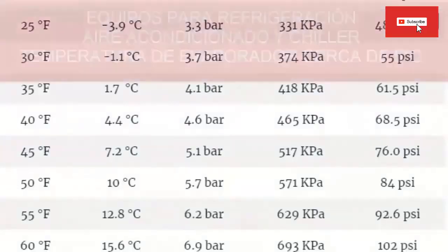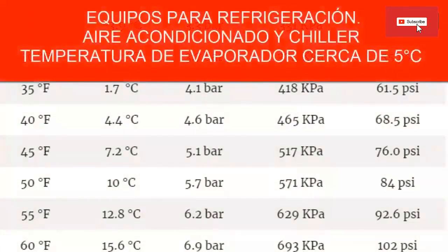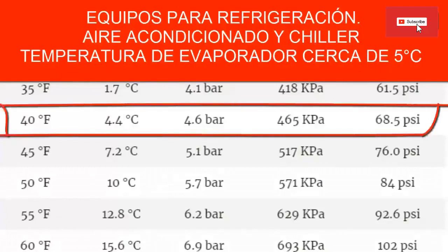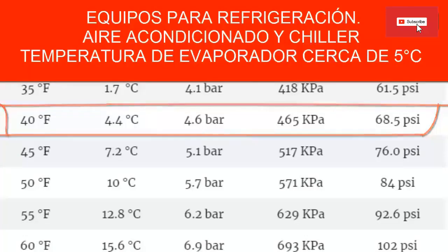For a high temperature system — refrigeration without freezing or air conditioning equipment — with a temperature of 4.4 degrees Celsius (approximately 40 degrees Fahrenheit), the low manometer should mark approximately 68.5 psi, equivalent to 4.6 bars.